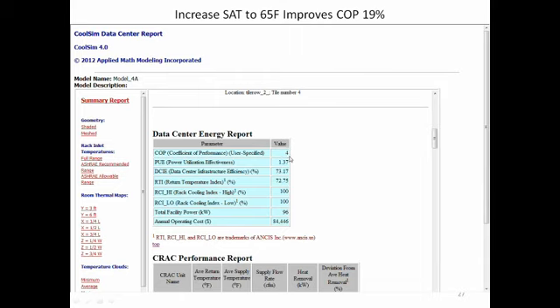Now the way I got that was to take the COP from the earlier run and just multiply it by the ratio of the temperature. In this case, I moved up 10 degrees of supply air temp, which gives me 19-20% improvement in COP. So I just multiplied 1.2 times my old COP to get the new one. So you can either use measured values on the input or you can use the COP value itself. You'll want to use them at different times. Originally I was using the measured values, but projecting forward, if I move up the temperature in the room, I used the COP value itself, driving the cost down to $84,000.